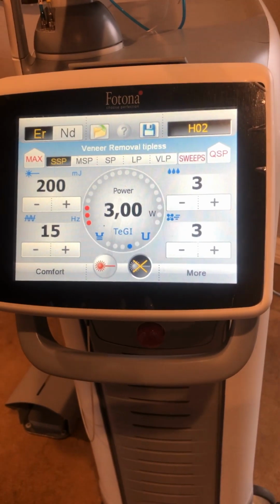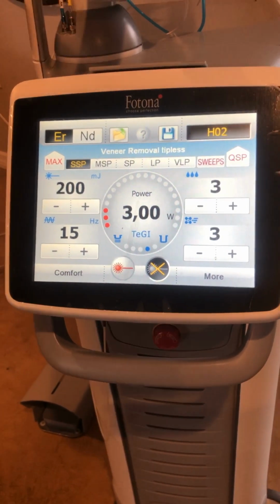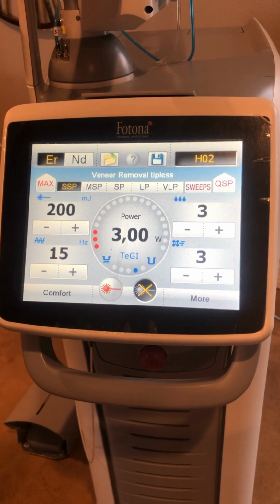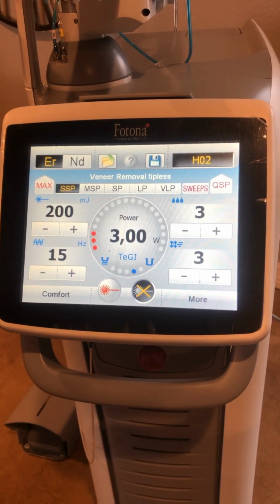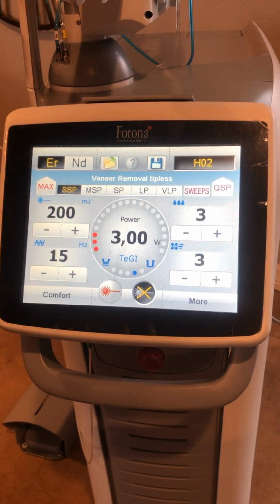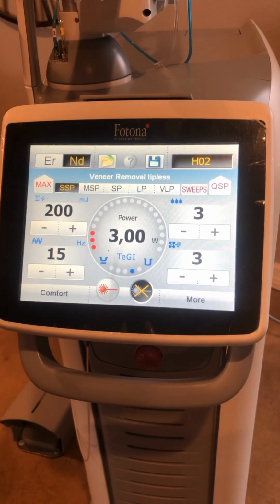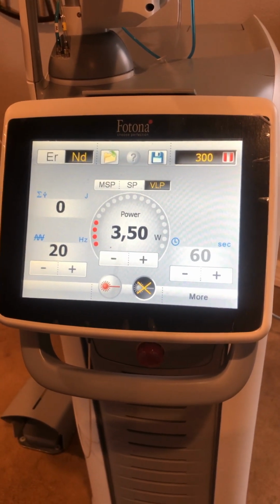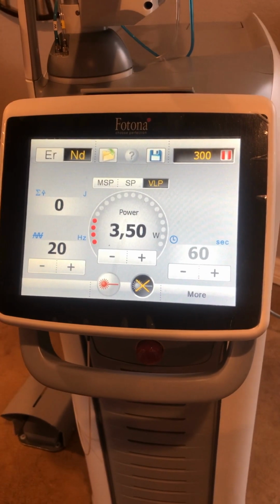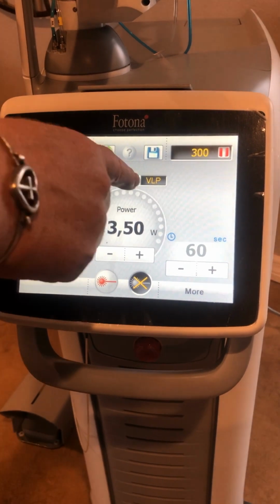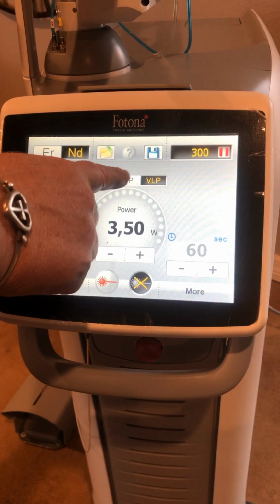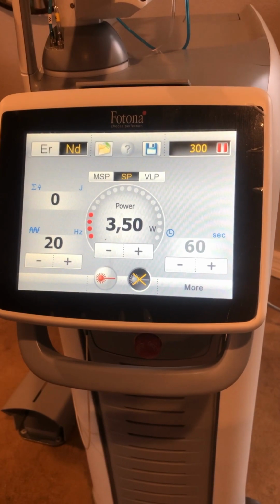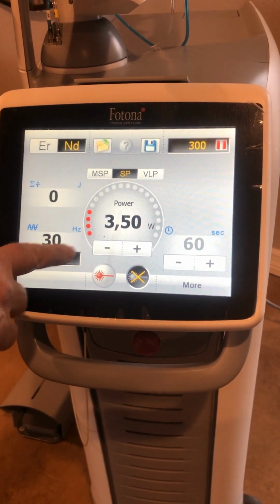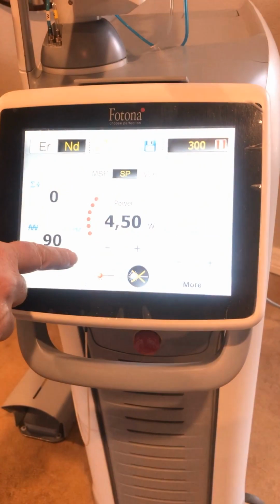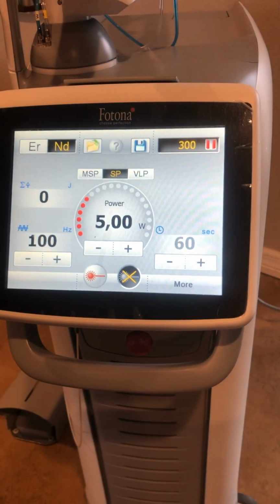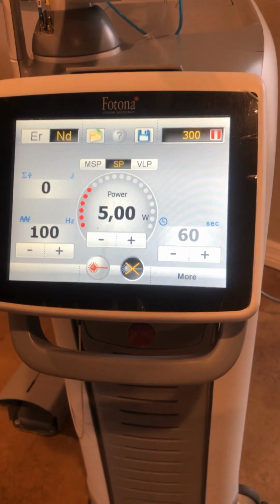And you can actually preset these the way you want. Let me show you how to actually save a preset that you might want. So we go in here and we're going to select the laser that we're using first. I want to use an Nd:YAG on this preset that I'm going to put in. And I want to use the 300 fiber, which is already set, which is great. And then I'm going to choose my pulse duration, which I want an SP, which stands for short pulse. And then I'm going to go up to 100 hertz, which should give me a total of 5 watts.